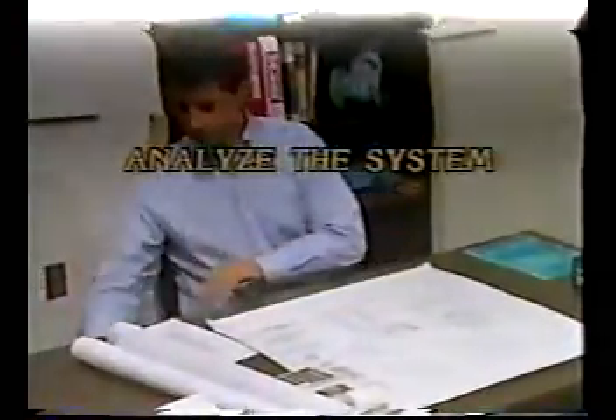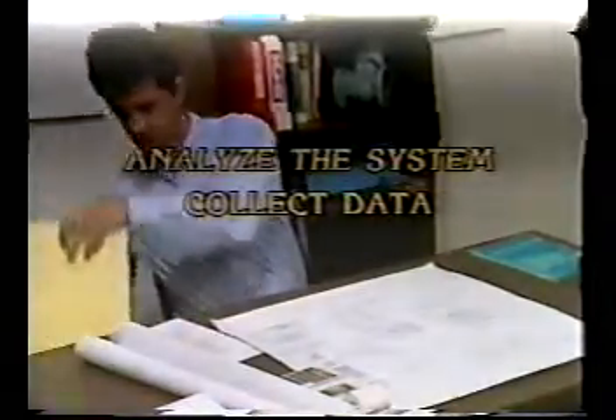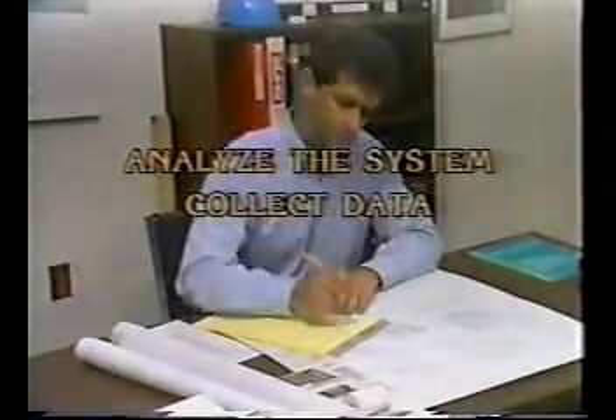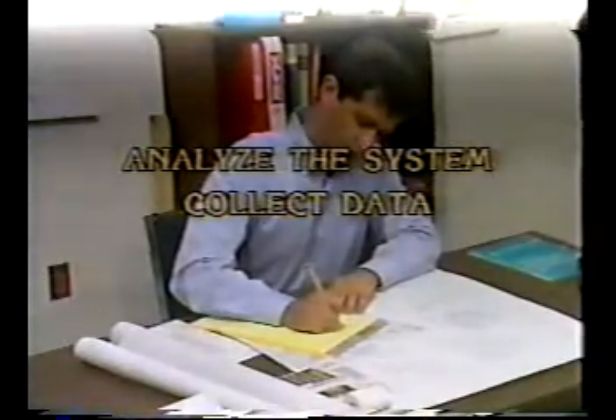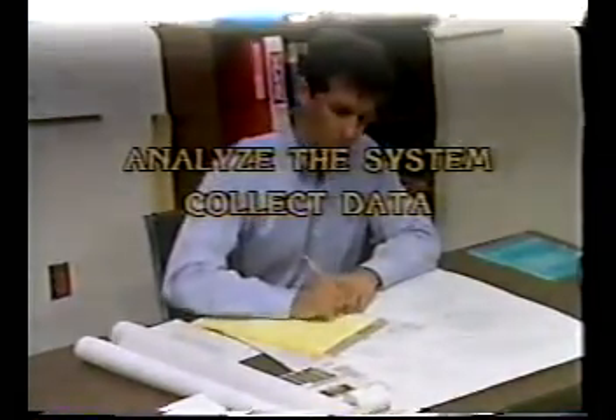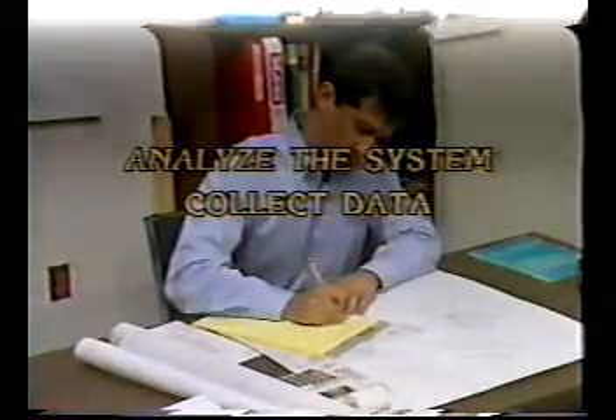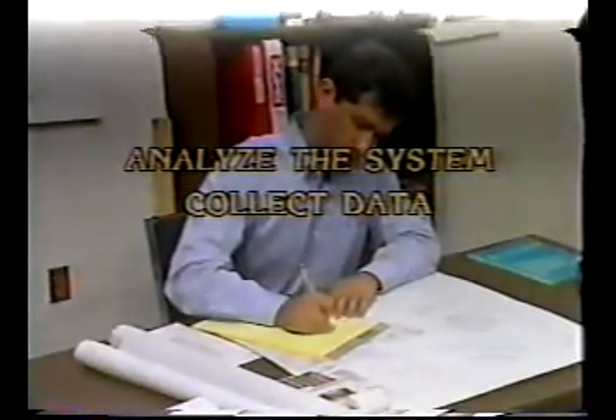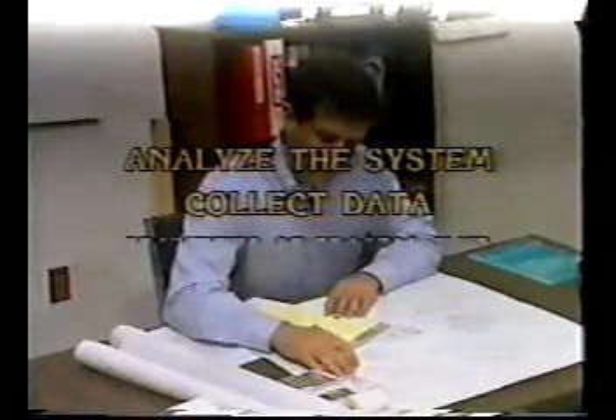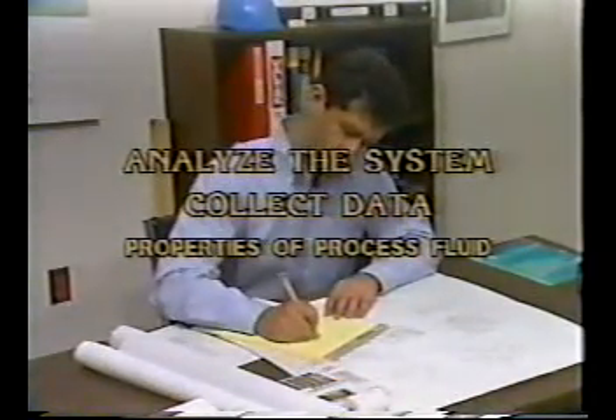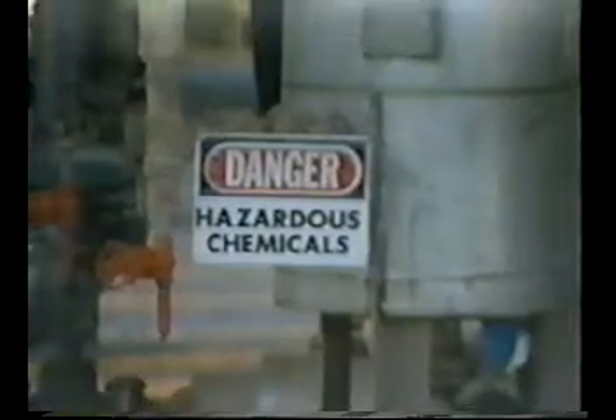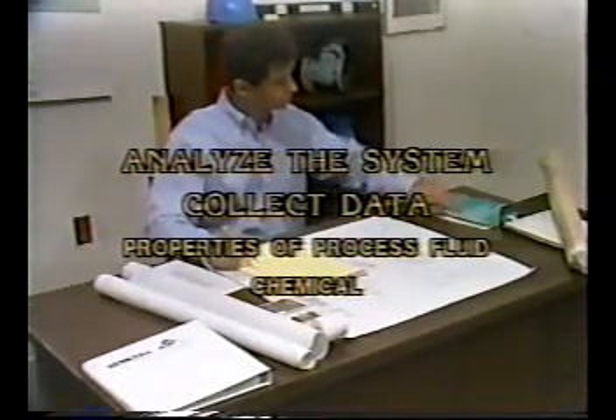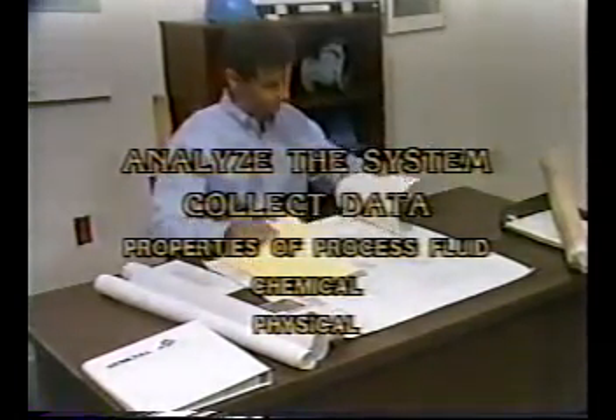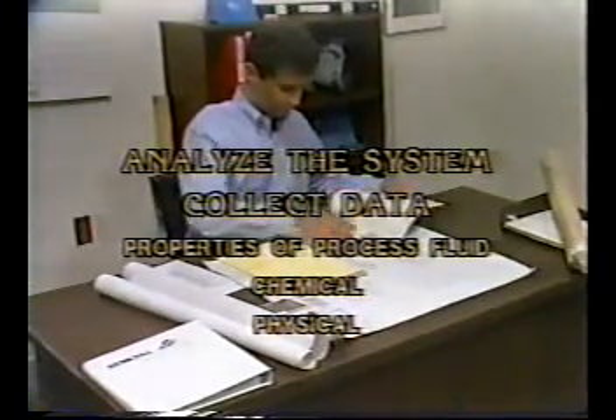After analyzing the system, you must collect and record data that will be necessary for proper sizing and selection. Now, some of this information you may already know, for instance, the required fail-safe action of the valve. But obtaining other information may require some research. You'll need information regarding the properties of the process fluid, as it will exist at the valve inlet. This includes chemical properties of the fluid, which may influence final valve selection. In addition to the chemical makeup of the fluid, the physical properties of the stream also need to be established.